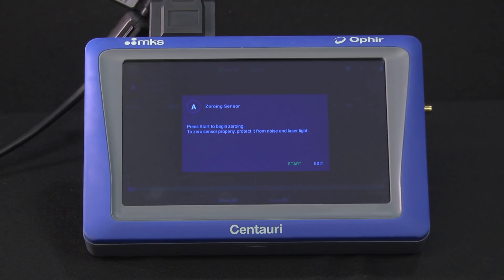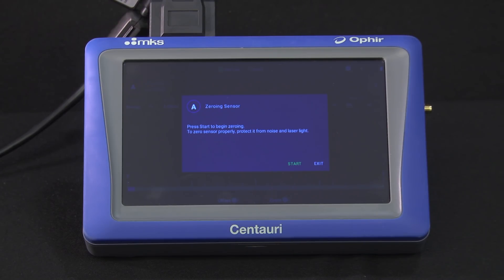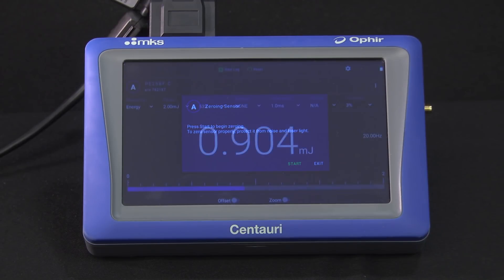Once done, you won't need to do that again for this sensor as long as it's being used with the same meter type — in this case, Centauri. When you change meter types, you'll want to re-zero the sensor.